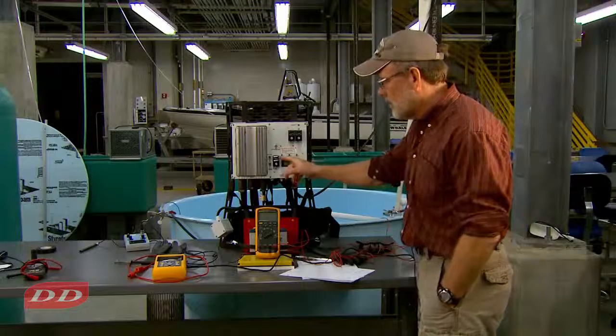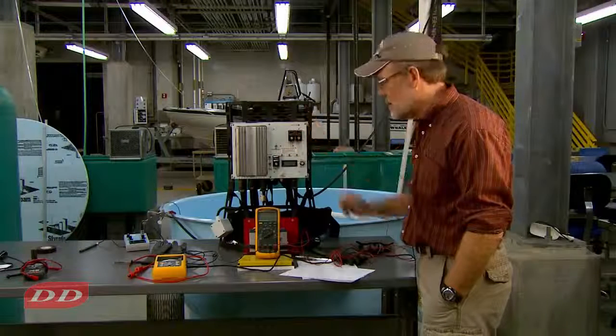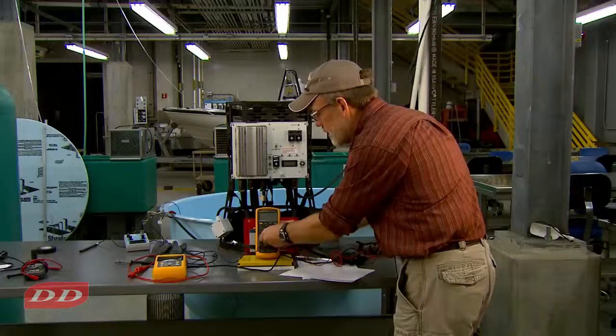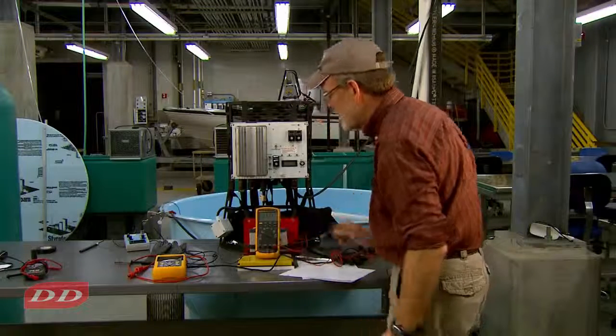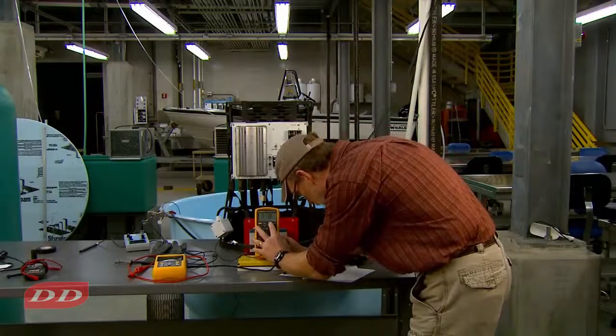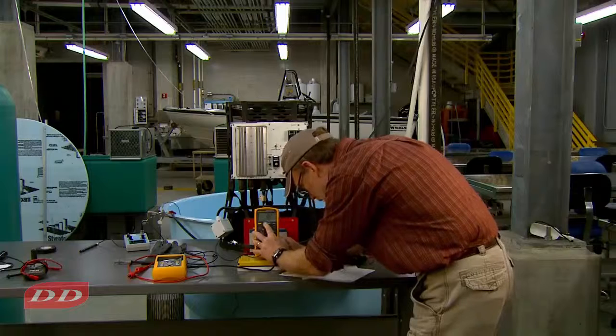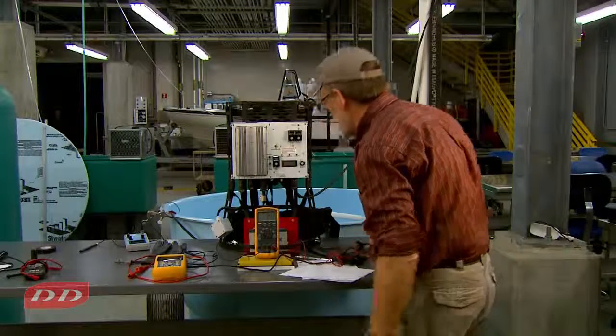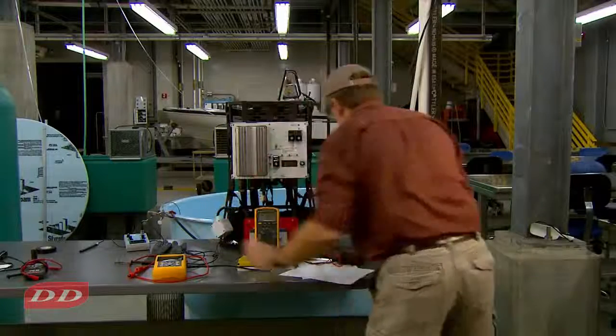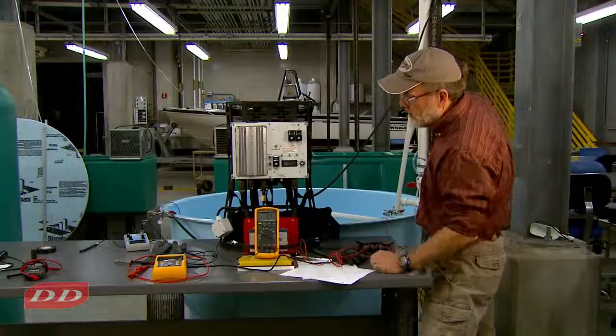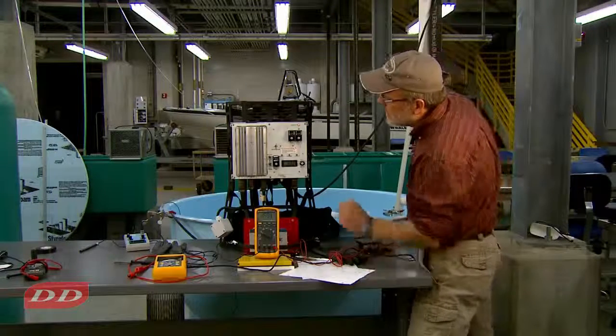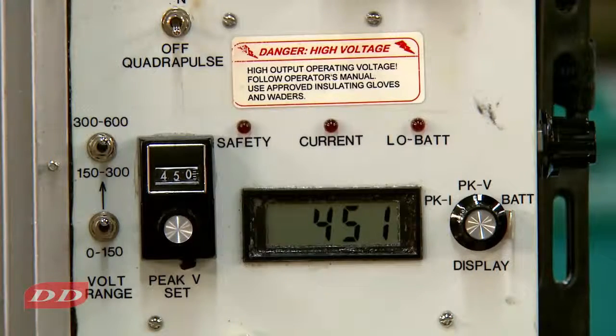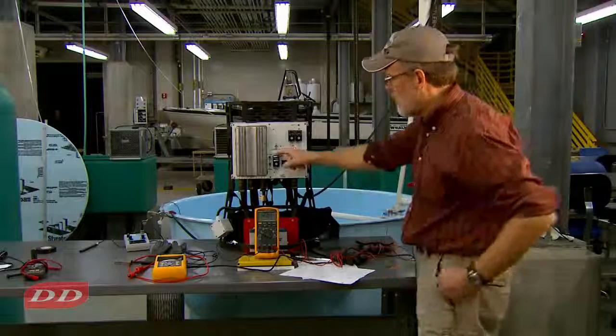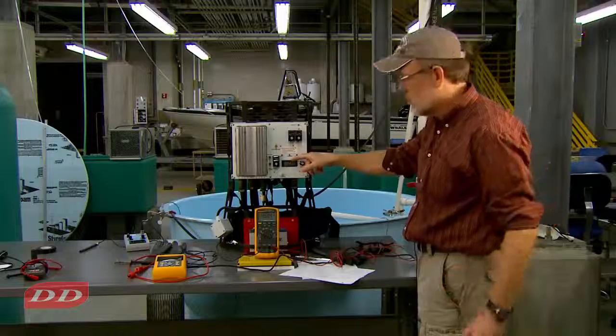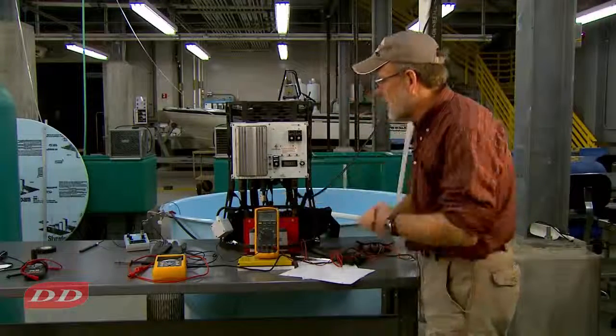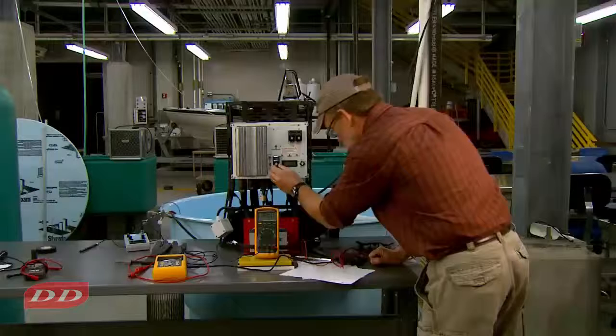So anyway, we'll continue this voltage calibration from 450 on up, and see where we get. I'm going to turn the dial on the multimeter to DC voltage, get the range about 600 volts here, and then tell it to read peak voltage. Got the dial set at 450. Now at a new water conductivity of 145, we'll go ahead and fire it up. And we have a peak voltage reading now of 451. So 450 set, 451, good correspondence, and on the multimeter, 460. So pretty close agreement.